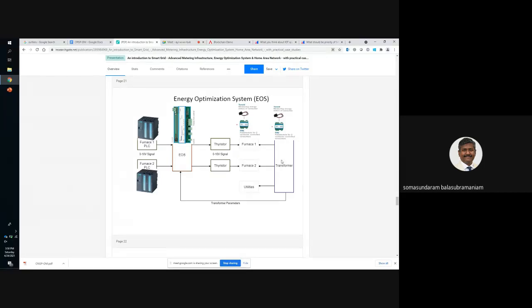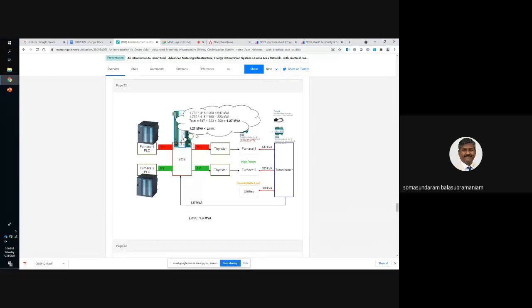There is a small algorithm which always checks whether the transformer load is less than 1.27 MVA, which is the ideal load for that particular transformer. It checks, okay, what is 100% the furnace is asking for energy - in terms of 10 volt is 100%, 5 volt means 50%. It does a quick calculation to see whether there will be an overload of the transformer. If there is no overload, it allows the reference to come to the thyristor.